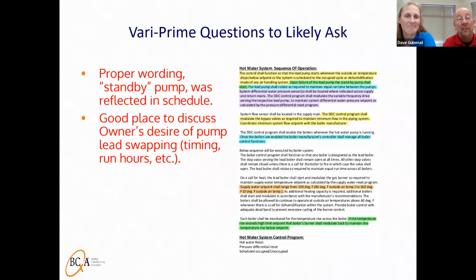This is just, again, examples of the designer and then the control contractor. They used the proper wording for standby, that it was a 100% redundant pump. The second pump would not have to run. But this is another good place where maybe it didn't get into much detail: how are we going to swap the pumps? Is it strictly timing, once it gets above X hours, which could be on New Year's Eve, 2 in the morning, minus 20 degrees outside, which would be a bad time to decide to switch the pumps?